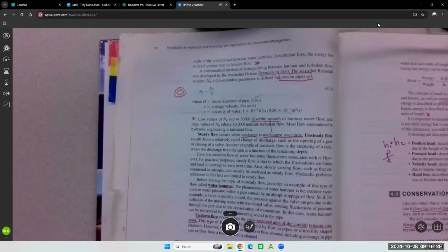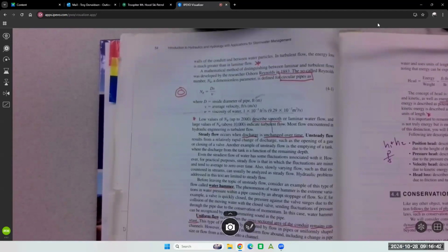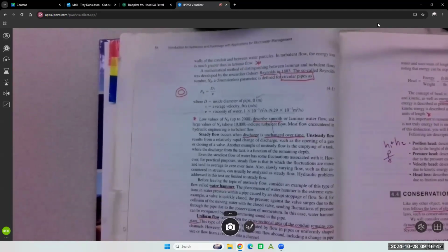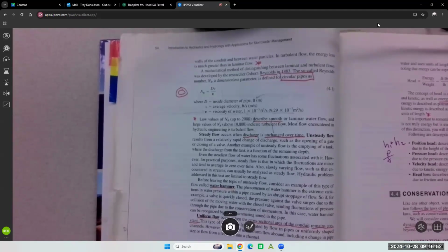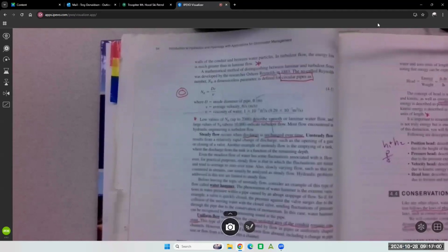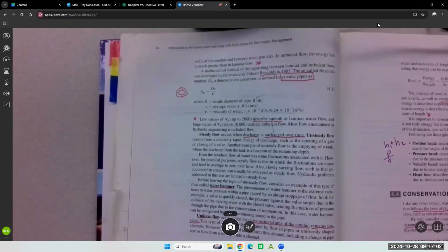Is there a name for an in between? Is there a mix of the two? The only thing I have ever heard is strongly laminar, and I've never heard anything for turbulent other than just turbulent. Yeah, potentially. So you can get a feel for that from the range. If I ended up with a 2,500 number, I'd say we're pushing towards a laminar flow, but might have turbulence if I have too many 90s that would build it up. If I came up with a 30,000 number, that's definitely turbulent.